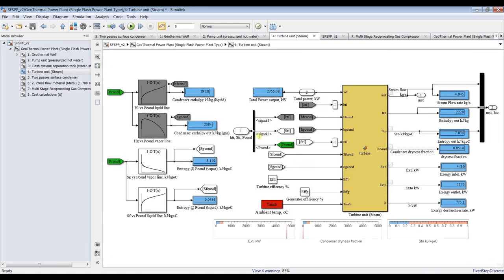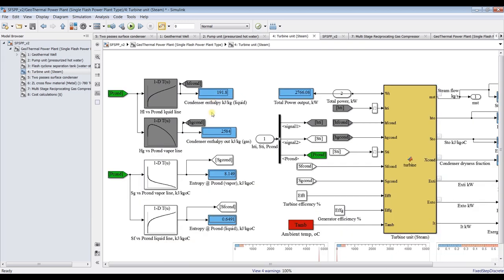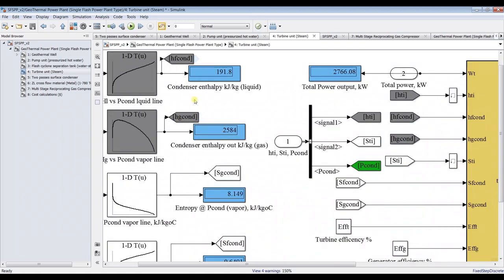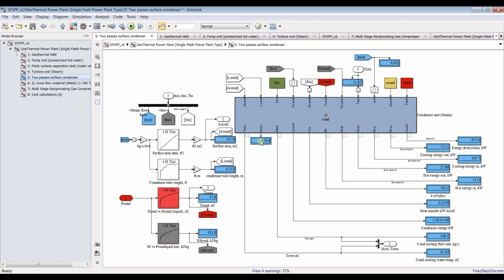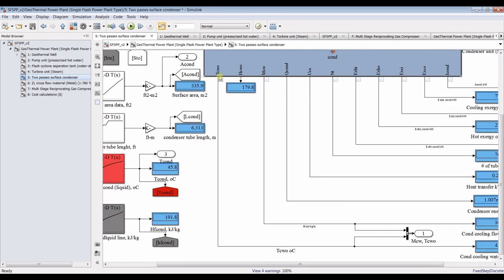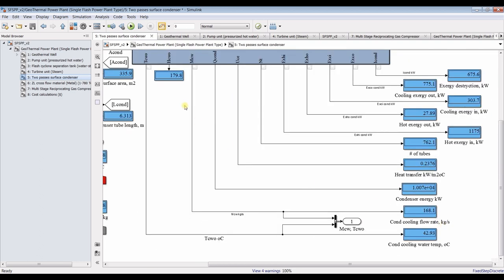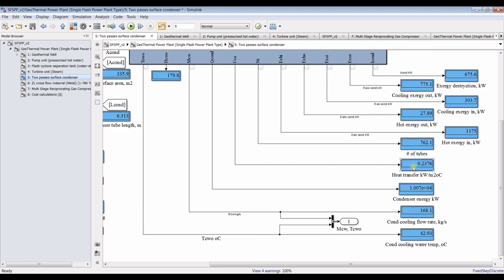Inside the turbine unit we can also discover condenser-related quantities: dry and liquid-state enthalpy and entropy, needed to calculate dryness fraction. For the two-pass surface condenser, outputs include: cooling water outlet temperature — approximately 42 degrees Celsius — condenser mass flow rate, heat transfer coefficient, number of tubes, and exergy for hot and cold streams (in and out). Hot stream inlet comes from the turbine; hot stream outlet goes to the pump. Cooling water is pumped back to the cooling tower, and cooling inlet comes from the cooling tower.